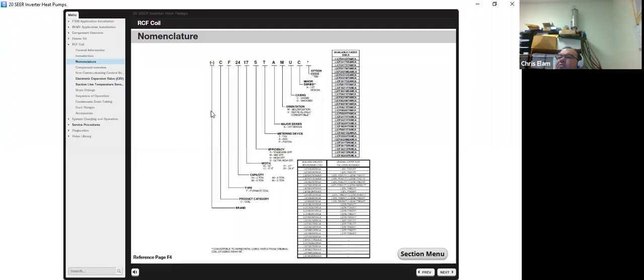The standard nomenclature here, the first letter is whatever brand it is. In this case here, Rheem. The C is your coil. This says F. It's a furnace coil. The next one will give you your capacity. In this case it's 24. The next one is your width. The next one is your efficiency. So you have your choice of standard, mid, high efficiency, or ultra efficiency.